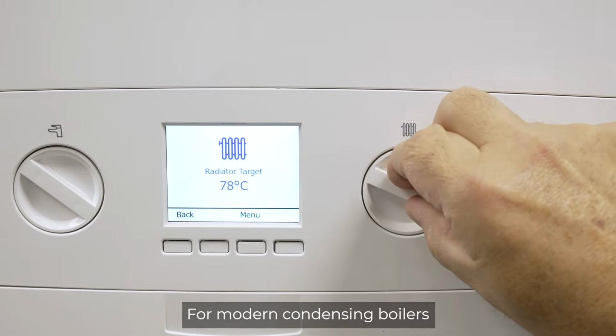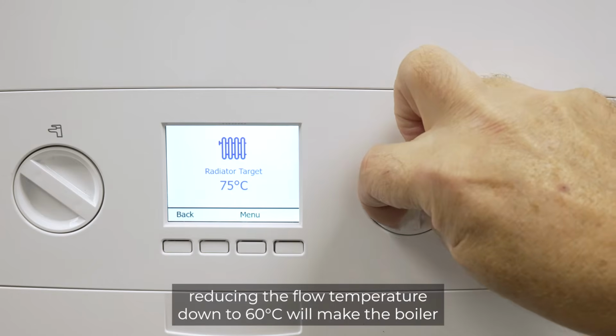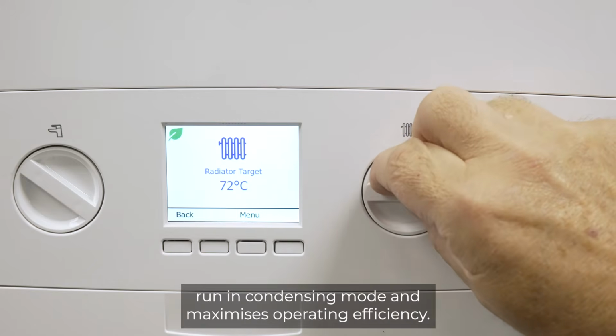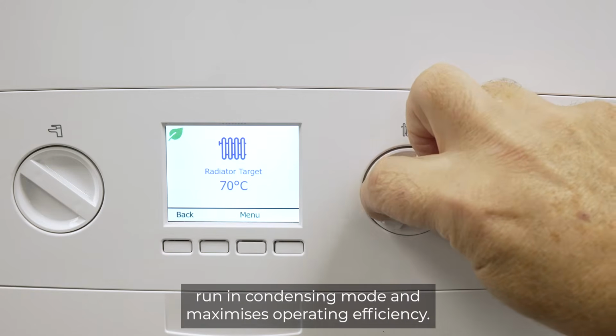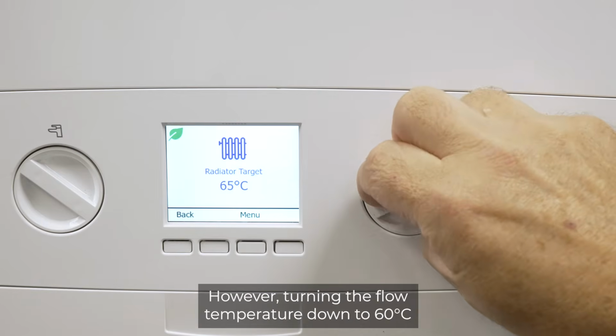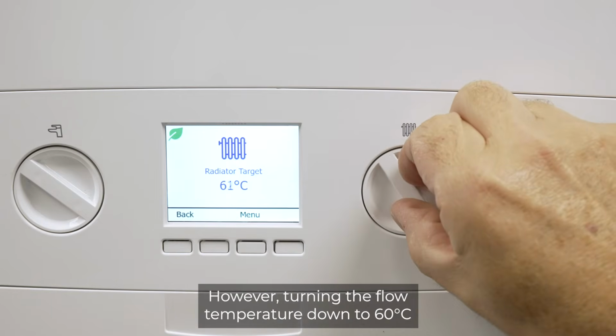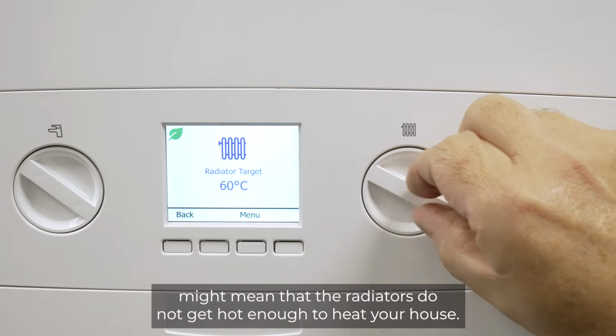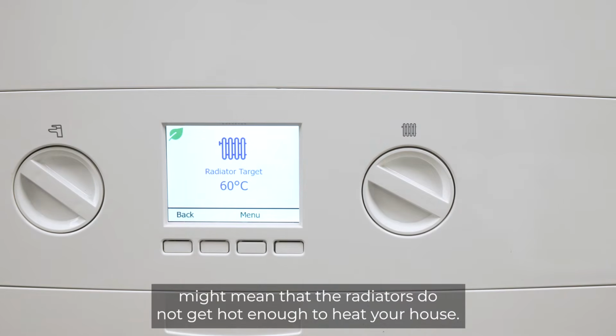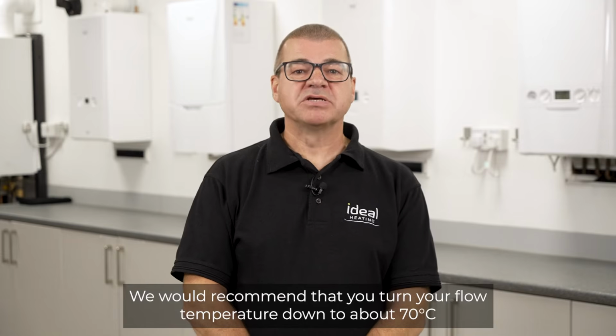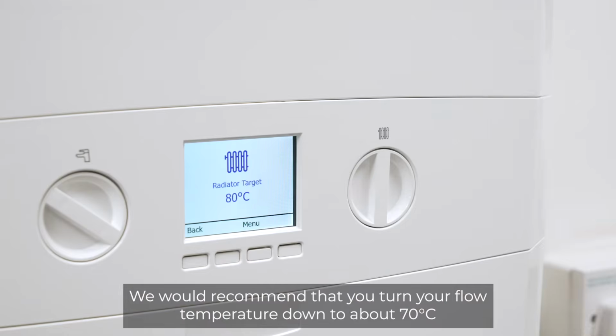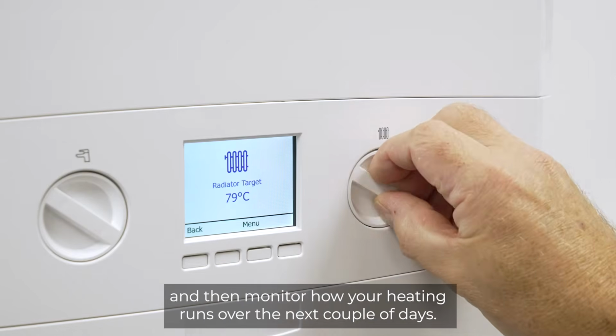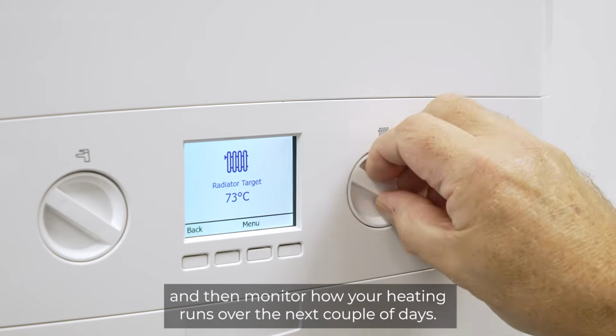For modern condensing boilers, reducing the flow temperature down to 60 degrees C will make the boiler run in condensing mode and maximise its operating efficiency. However, turning the flow temperature down to 60 degrees C might mean that the radiators do not get hot enough to heat your house. We would recommend that you turn your flow temperature down to about 70 degrees C and then monitor how your heating runs over the next couple of days.